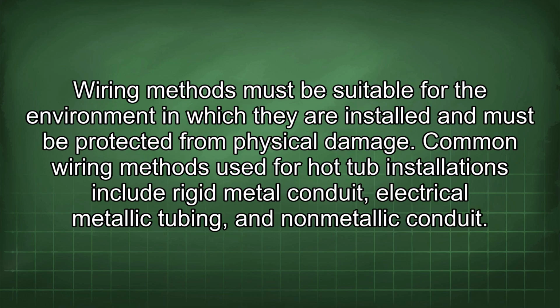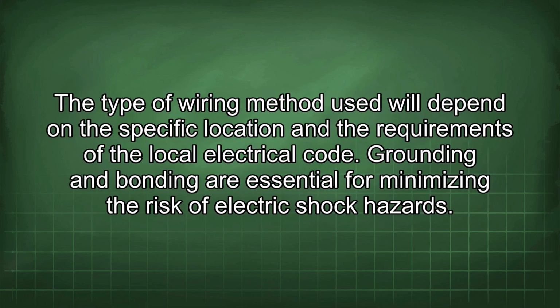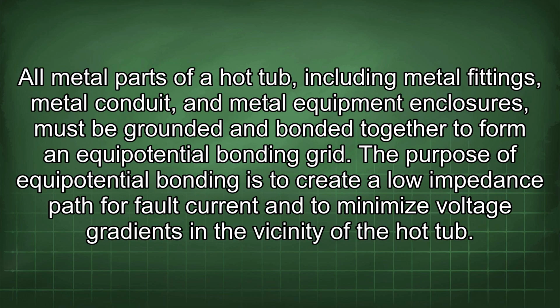Wiring methods must be suitable for the environment in which they are installed and must be protected from physical damage. Common wiring methods used for hot tub installations include rigid metal conduit, electrical metallic tubing, and non-metallic conduit. The type of wiring method used will depend on the specific location and the requirements of the local electrical code. Grounding and bonding are essential for minimizing the risk of electric shock hazards. All metal parts of a hot tub, including metal fittings, metal conduit, and metal equipment enclosures, must be grounded and bonded together to form an equipotential bonding grid.